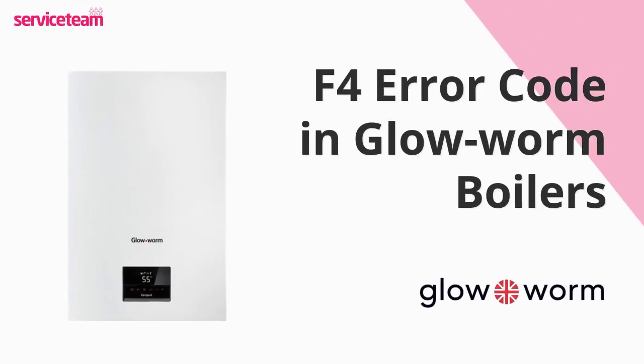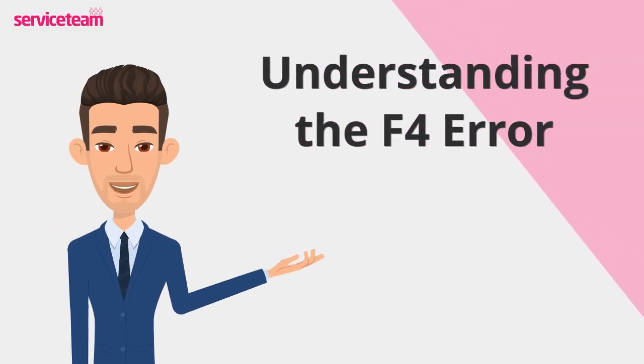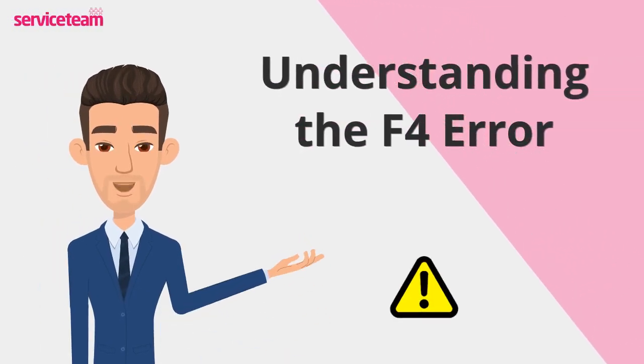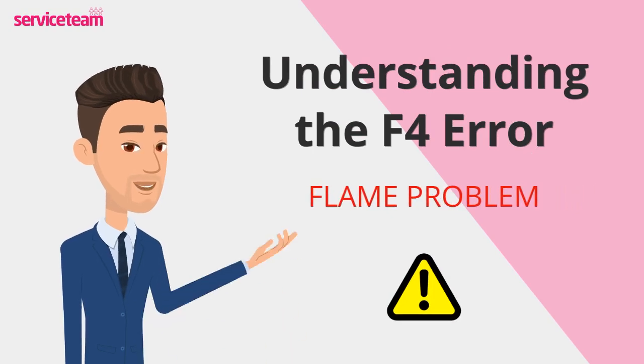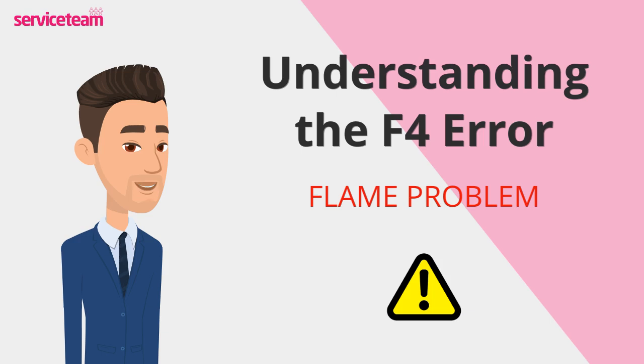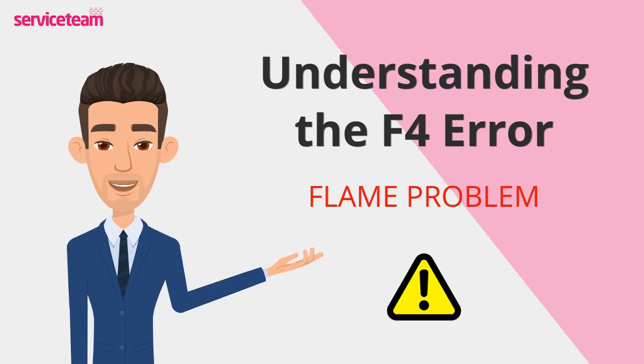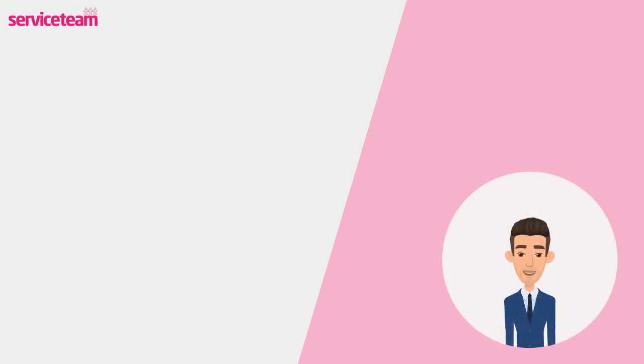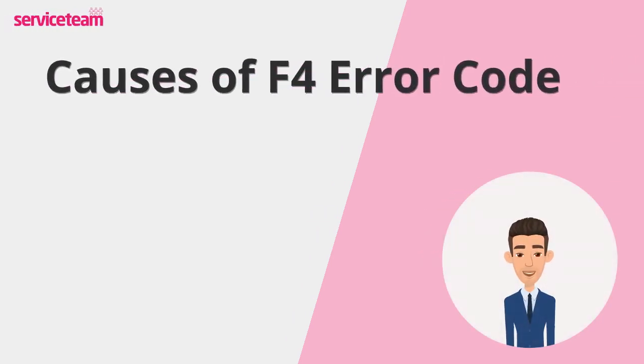Let's check out how to resolve the F4 error code on the Glowworm boiler. When your Glowworm boiler shows the F4 fault code, it means the boiler can't detect a flame. Boilers need a steady flame to burn fuel and generate heat, so if the flame isn't there, the boiler shuts down as a safety precaution. This lockout prevents risks like gas leaks or overheating, but also stops your heating system from working. Let's take a closer look at what might be causing the F4 error on your Glowworm boiler.